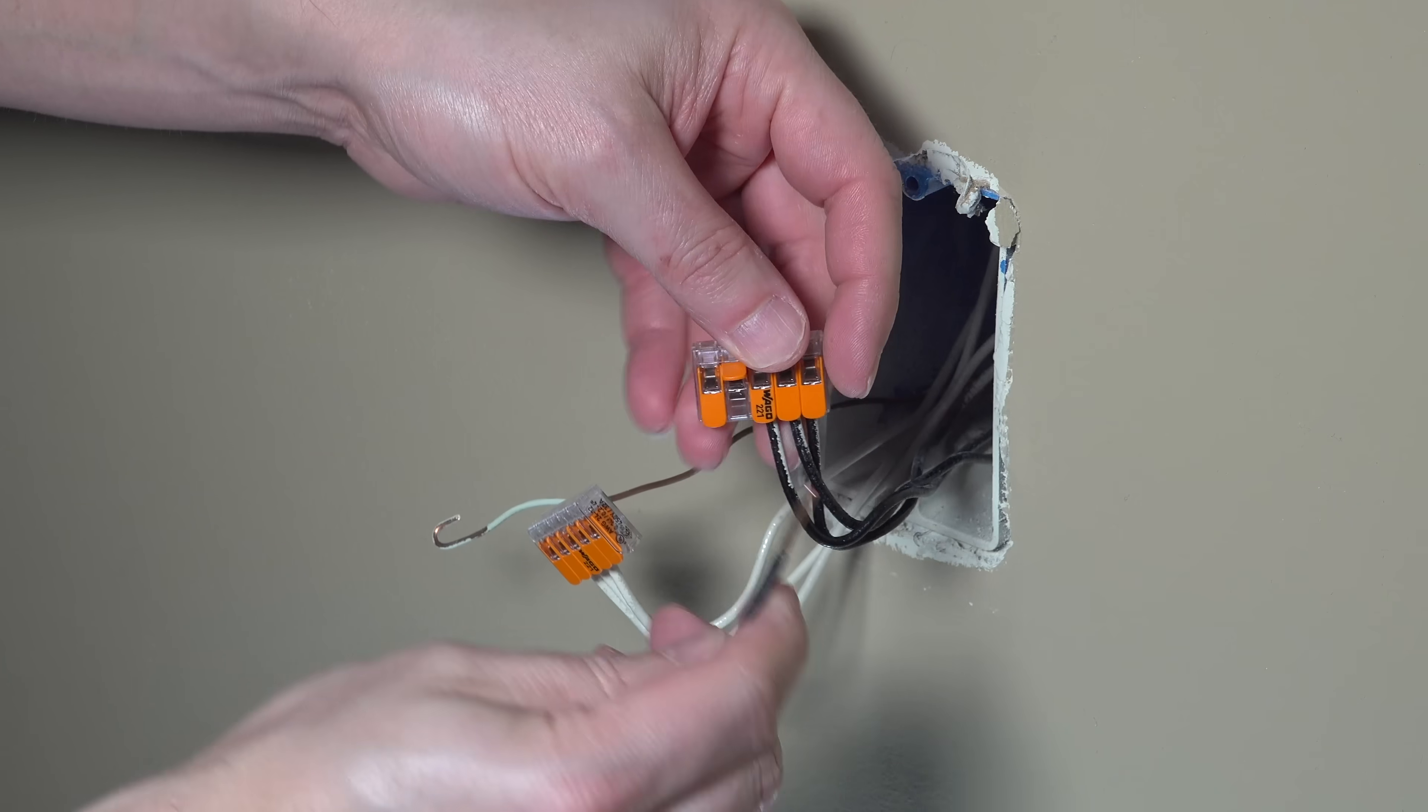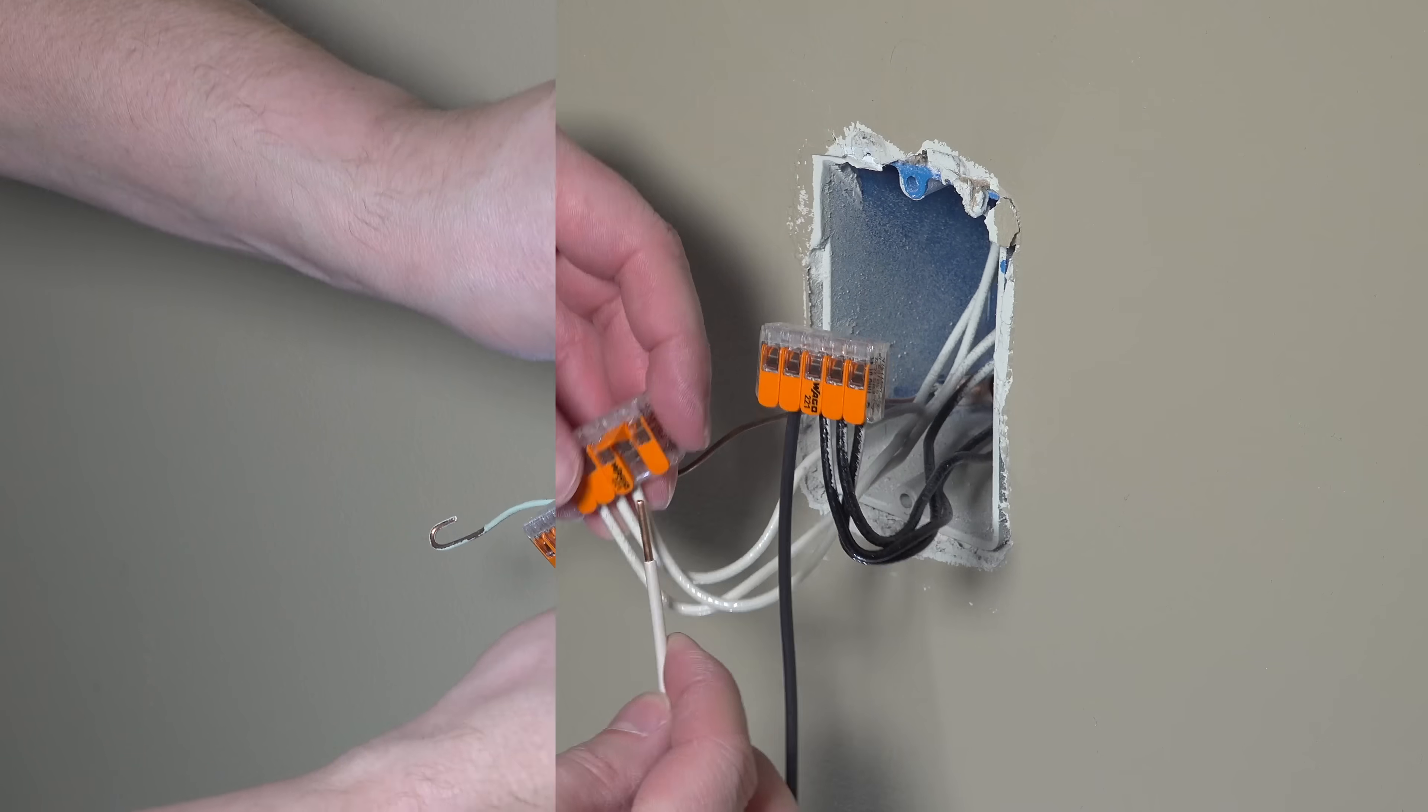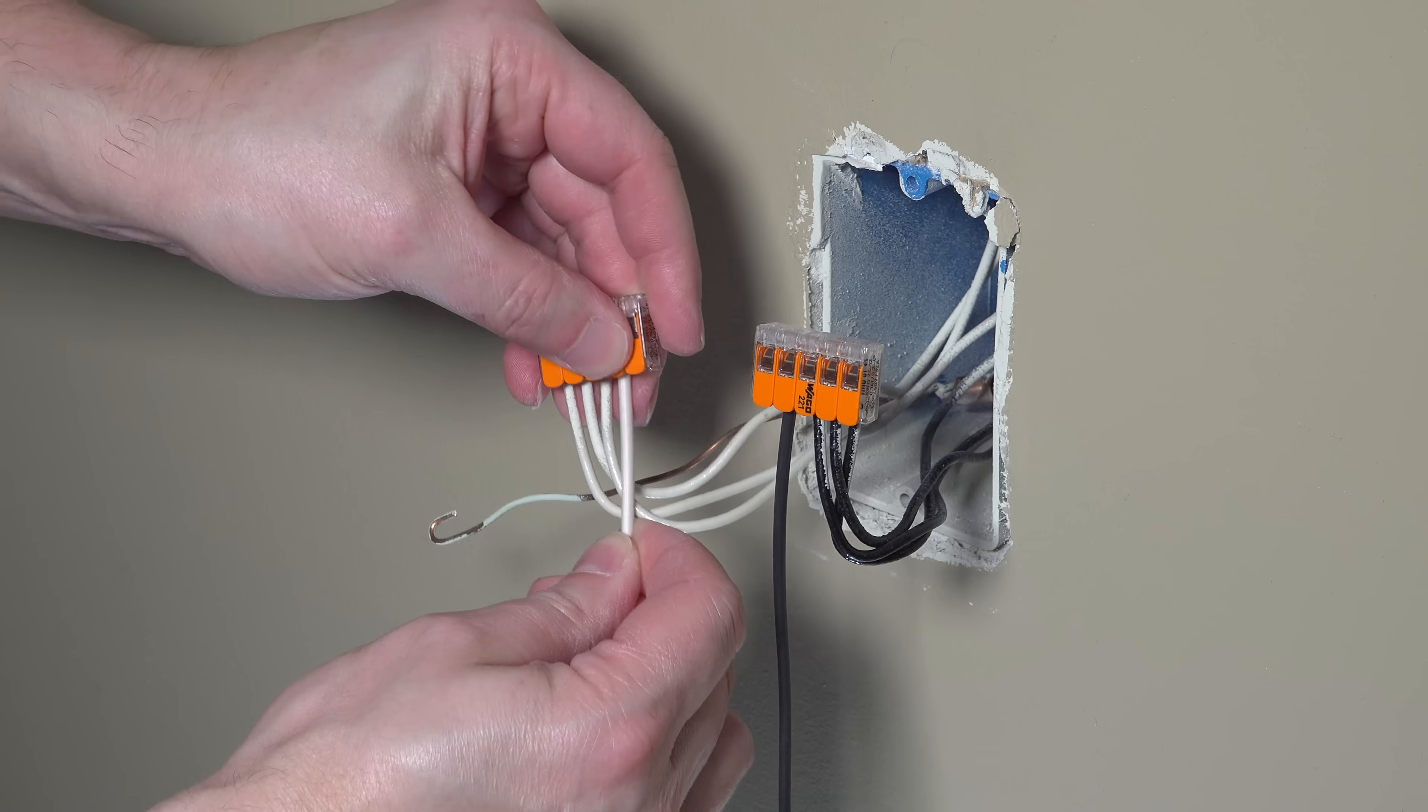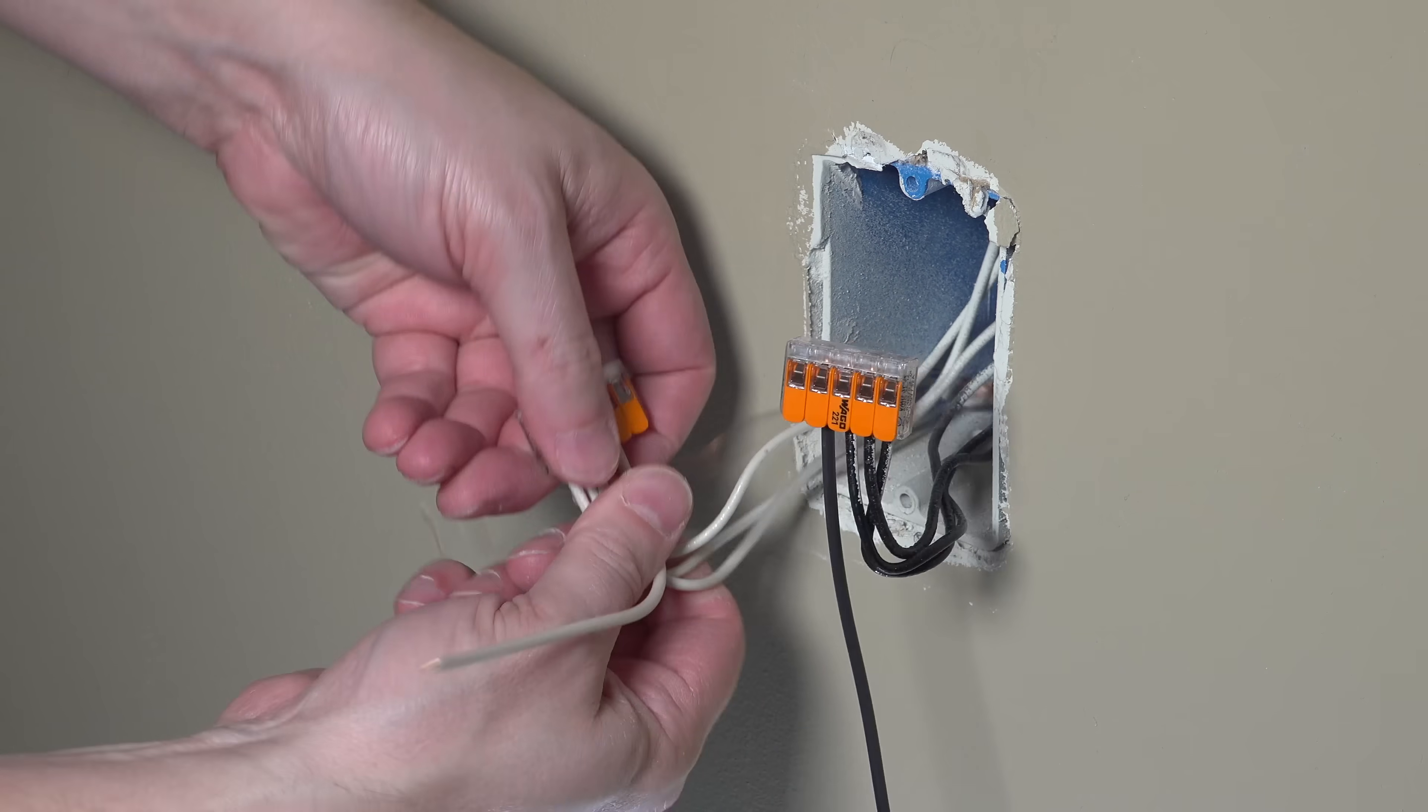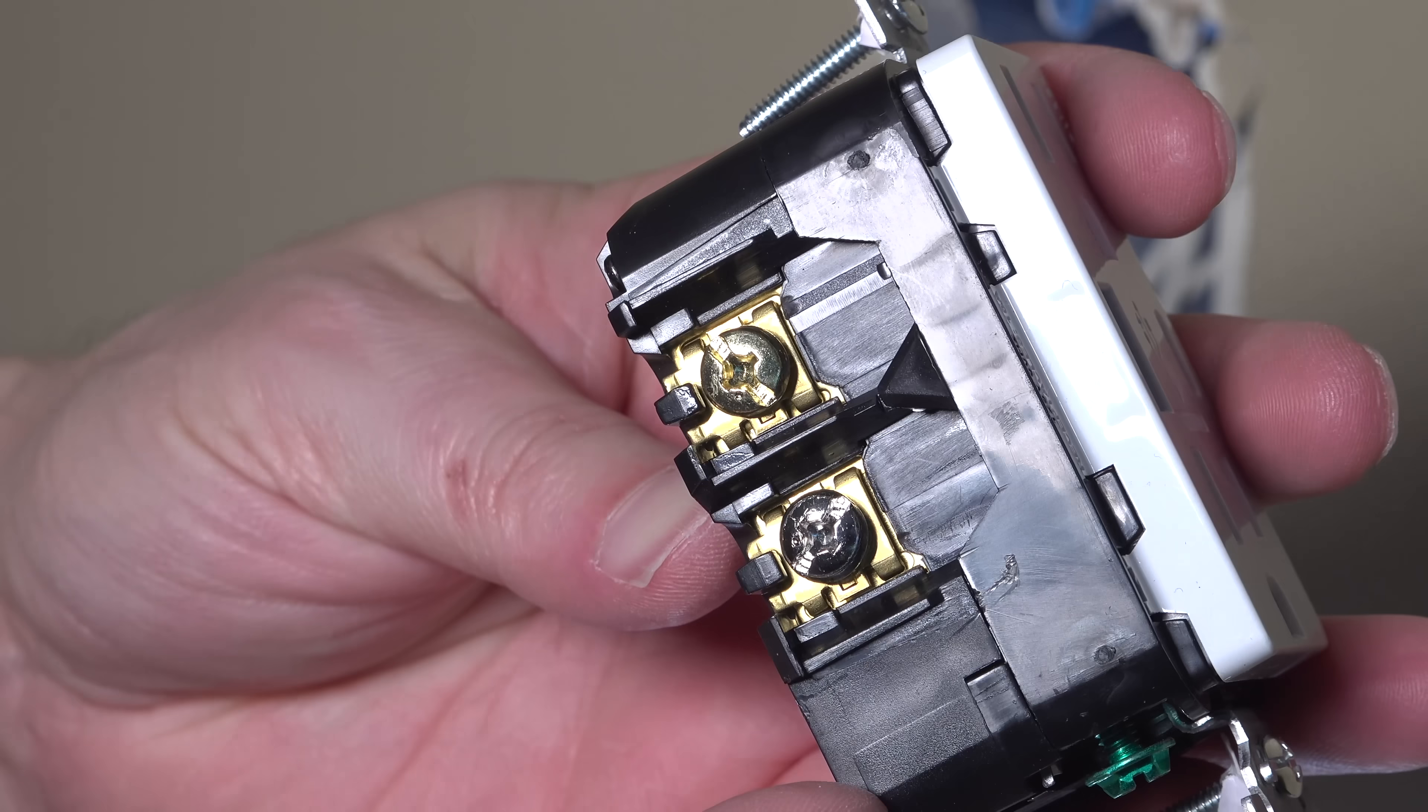Another important tip is that the wire used to pigtail has to be at least the same size as those wires in the junction box. Now we just need to make the final connections with our hot and neutral into the WAGO connector, and then we can strip off the other end of the wire and we're ready to connect it to our outlet.